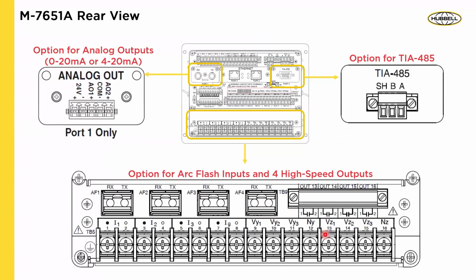Now, there are certain options, right? On the communication side of things, you could opt out of the serial port, and opt in for, let's say, an analog output board. You can have 2 analog outputs on that card, 4 to 20 milliamps or 0 to 20 milliamps. And on the 232 side, you could also switch to a 485 if you wanted it. You could have a 232 and a 485 both, depending on which card you pick. And at the bottom, you see there's voltage and currents. You could switch that out for optional arc flash protection. When you order arc flash, it comes with 4 arc flash sensor inputs, and then you have 4 high-speed outputs. These are your solid state relays and have outputs of less than a millisecond.